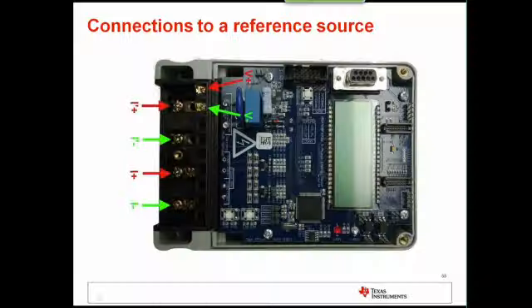This is what it'll look like coming out of the box if you're going to take it to a customer. For e-metering customers, they're going to have the test setup and reference connections to do this kind of thing in their labs. Here the voltage inputs are on these two terminals, and they're separated physically from the current inputs. This is a safety thing first off, for whenever you're doing design and test of these meters, to have these two separated so they're fully isolated from each other.